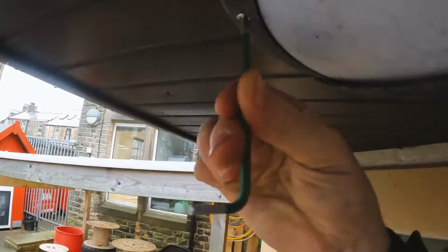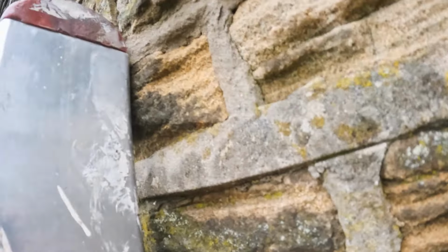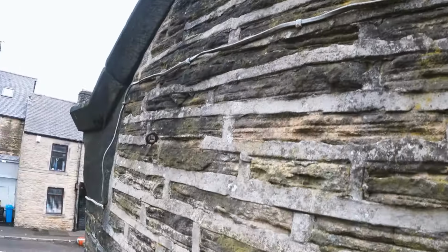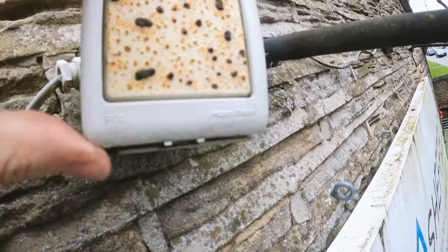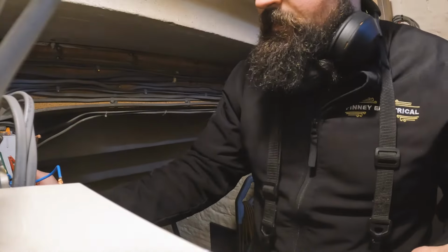Look at this, trash. Look at this. That's indoor cables running outside. It's got bad IR readings. Yeah, same circuit, 0.53. There's no switch in that. It's a light switch, it's coming up here. So there we go. It turns out it was them dodgy lights outside wired in the indoor cable.